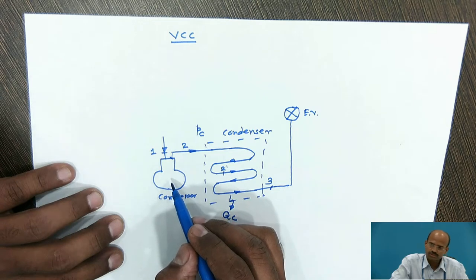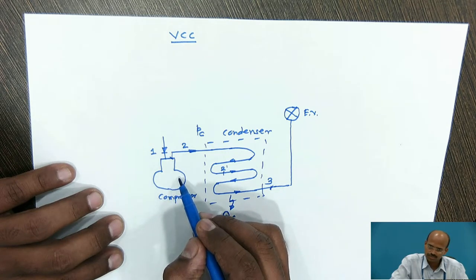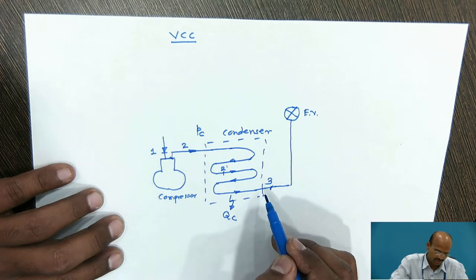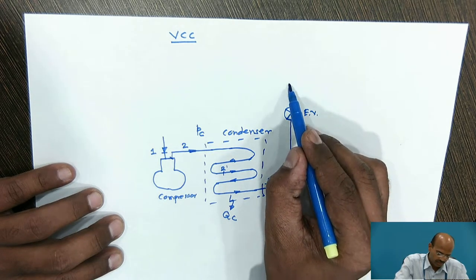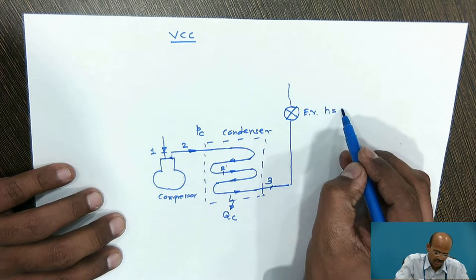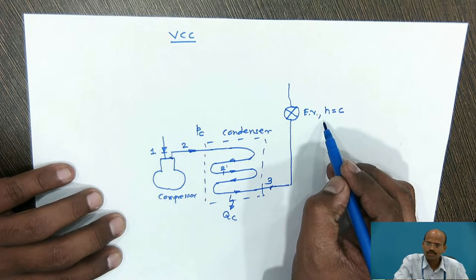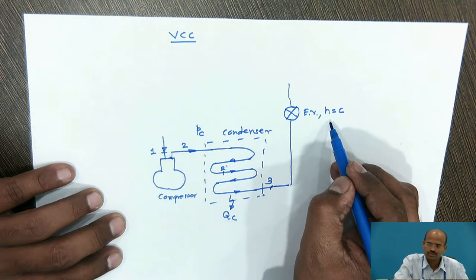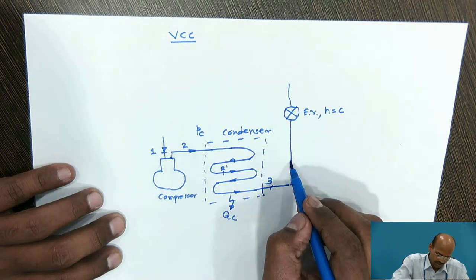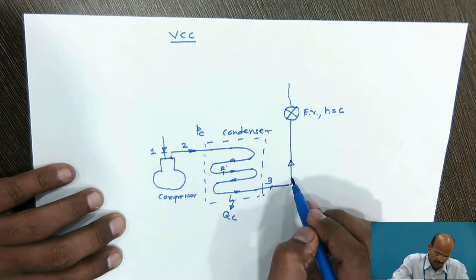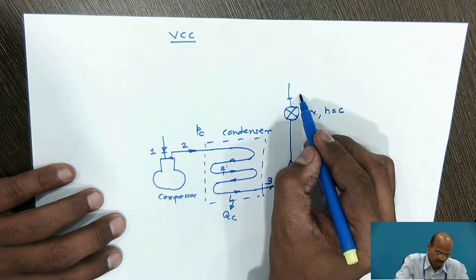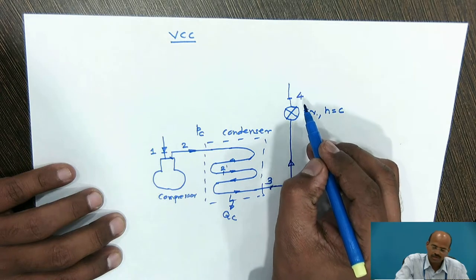The compression process is an isentropic compression process and the condensation process is an isobaric condensation process. In the expansion valve, the type of process that takes place is throttling, meaning the enthalpy during the expansion process remains the same. Therefore the saturated liquid undergoes the throttling process and at the outlet of the expansion valve we get low pressure wet refrigerant.